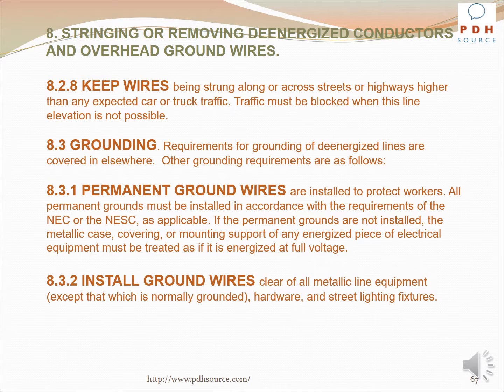Permanent ground wires are installed to protect workers. All permanent grounds must be installed in accordance with the requirements of the National Electrical Code or the NESC as applicable. If the permanent grounds are not installed, the metallic case covering or mounting support of any energized piece of electrical equipment must be treated as if it is energized at full voltage. Install ground wires clear of all metallic line equipment except that which is normally grounded, hardware, and street lighting fixtures.